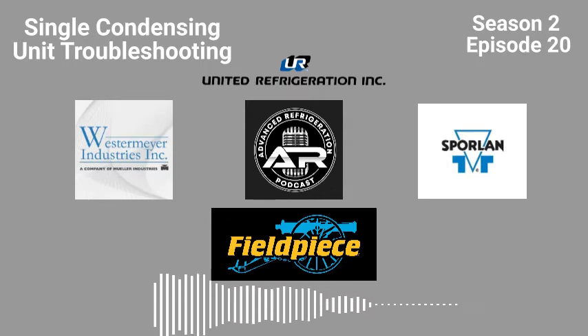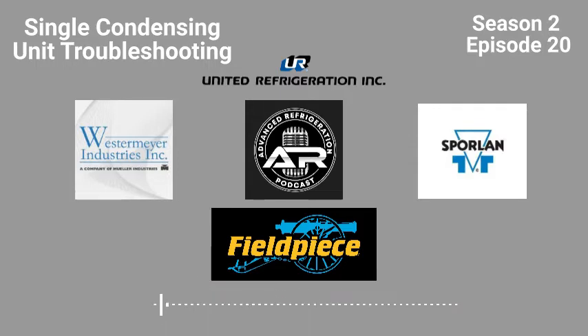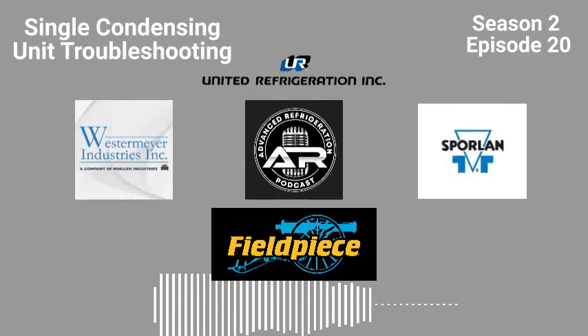So my fix for it for the time being. Go ahead. You almost need another case. Like you're almost short a case. Right. And that's what I'm thinking. Nice. Well, and or falsing the load, hot gas bypass, de-superheating, just bringing that pressure up to bring that saturated suction up just to have the capacity that you need. That's how Target's cheating the sizing when they get close.